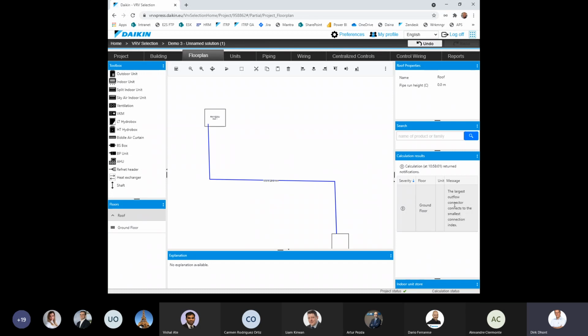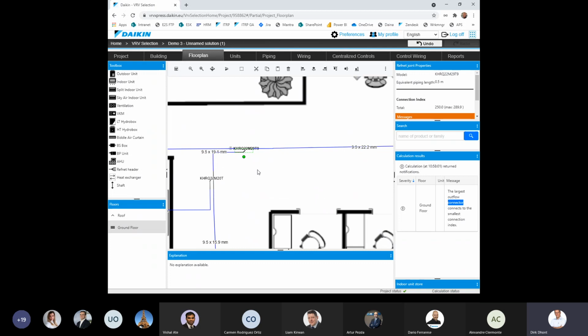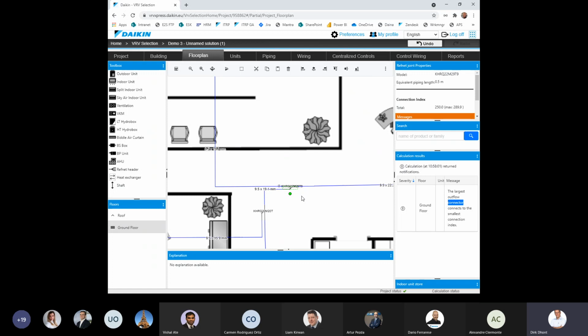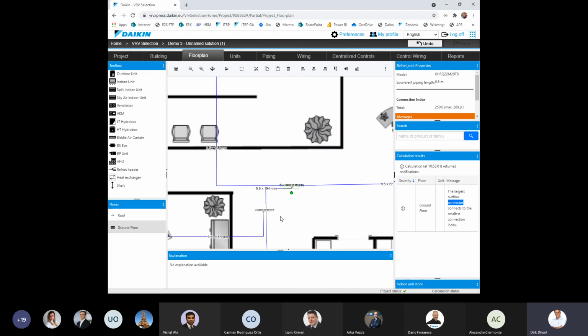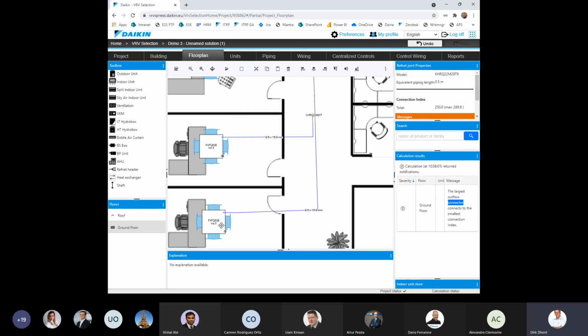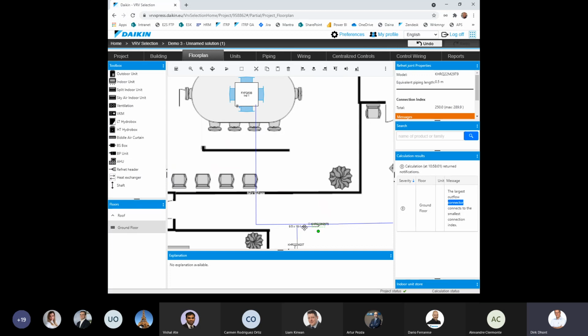What does that mean? Well, just double click on it and it highlights the location where the problem is being caused. So let's zoom into that. There is something with this RefNet. And what is it? Well, on a RefNet, you always have to make sure that the biggest connection index is on the main connector and the smallest connection index is in your divergent connection. And here it's the opposite way. So you see, for instance, that on the divergent connector, we have 3 times, I think, a 63 class end unit, while on the main connector, we only have once a 63.